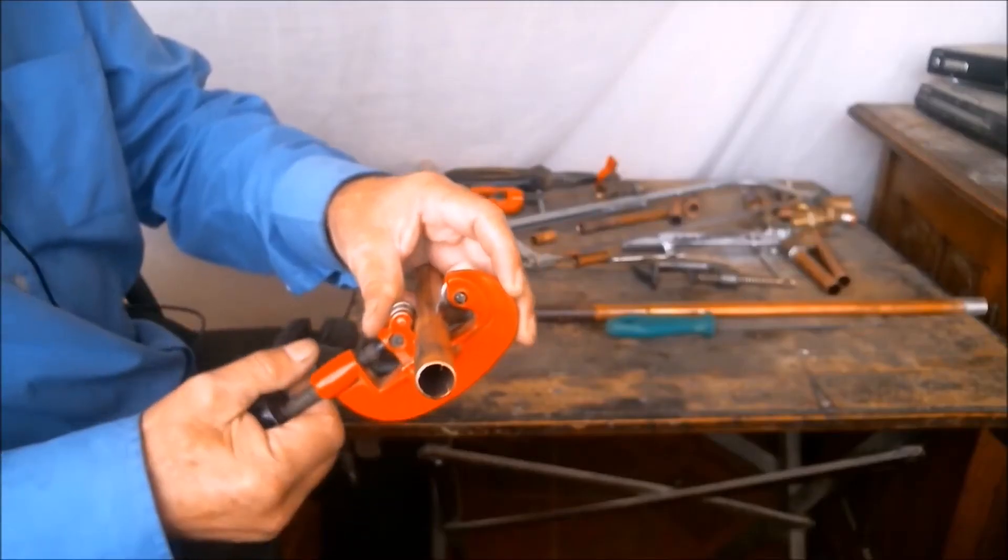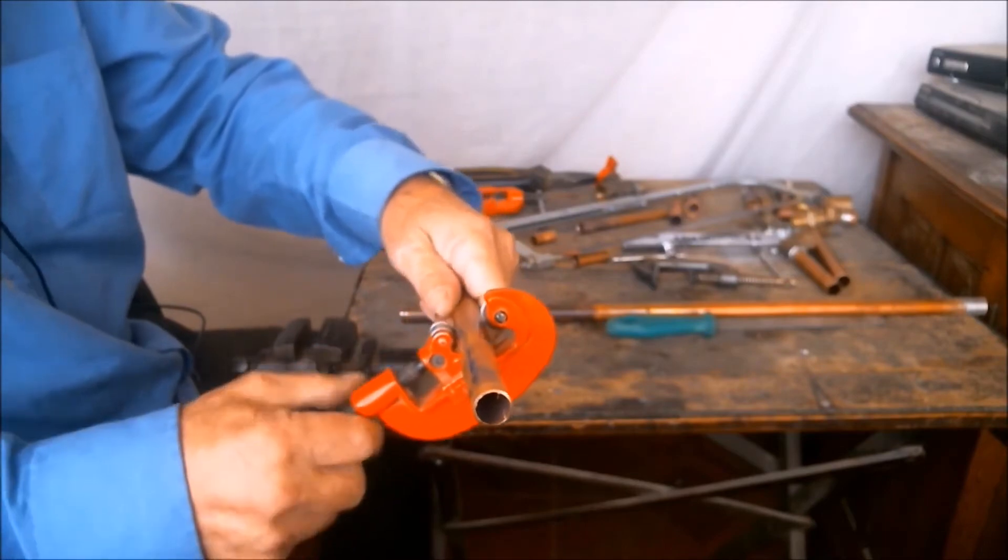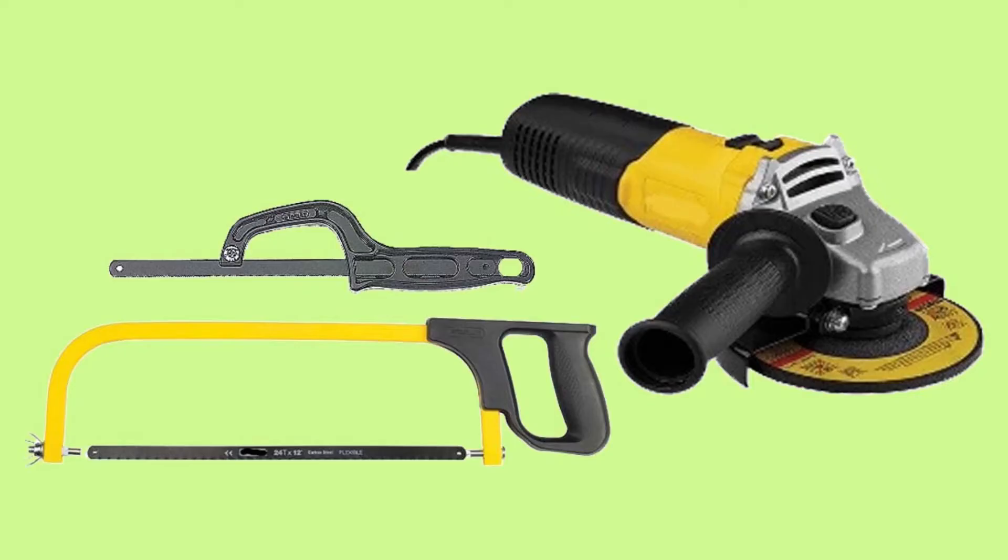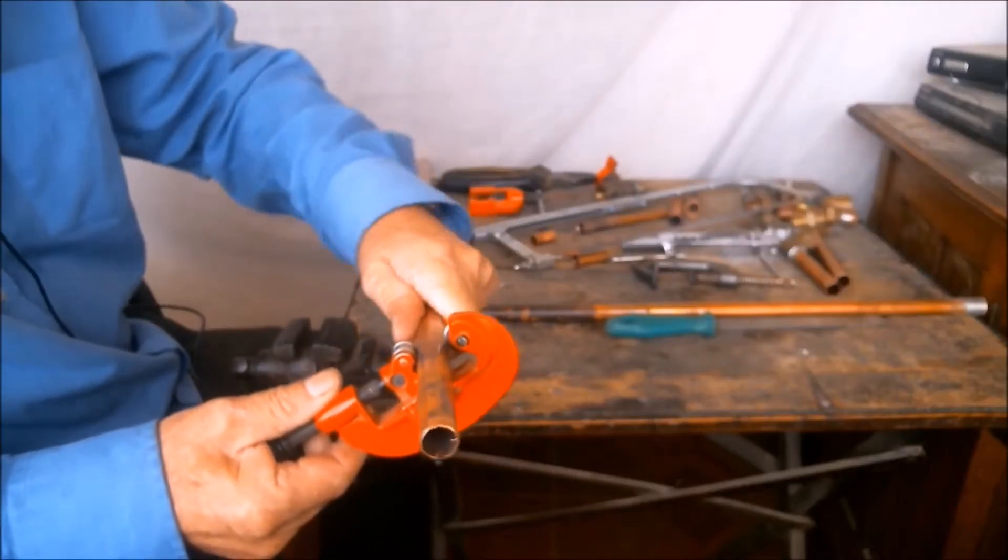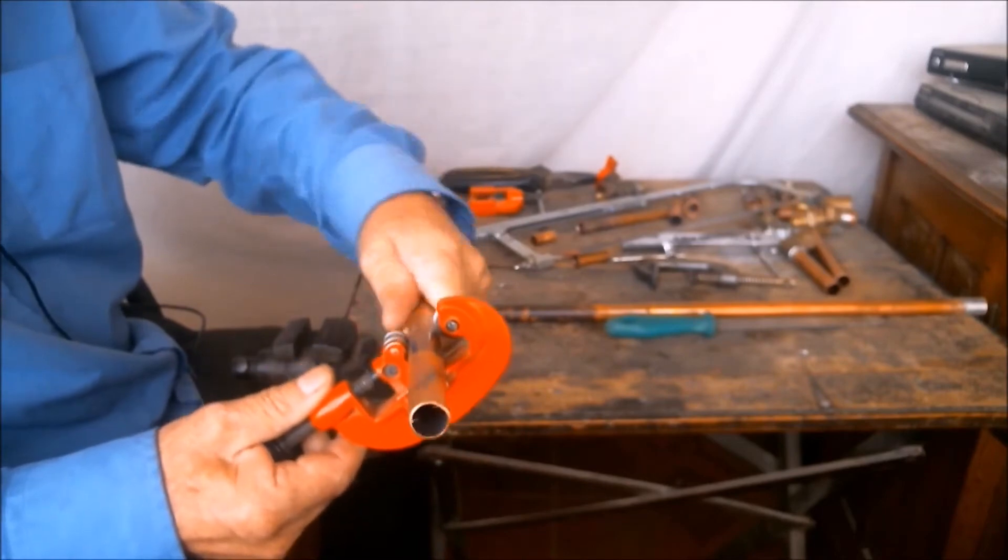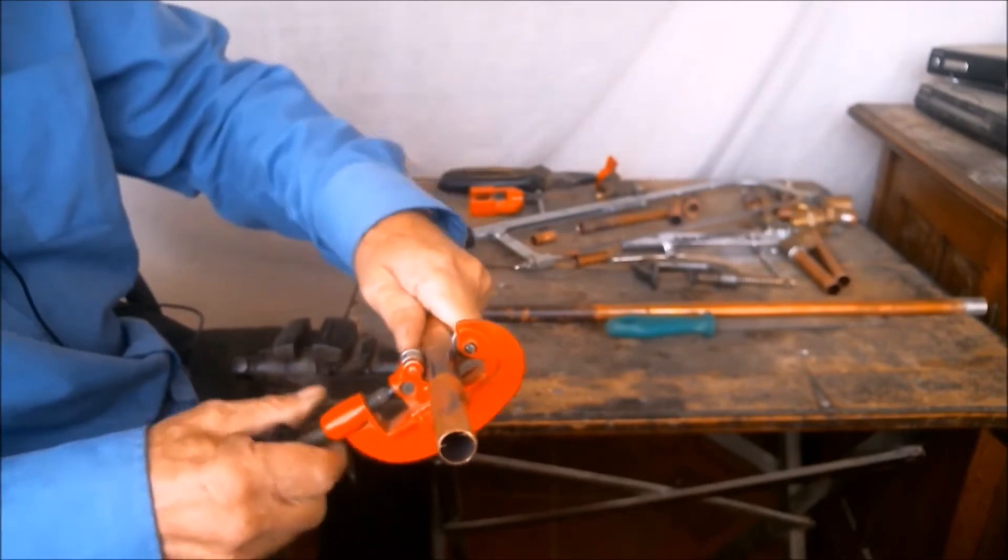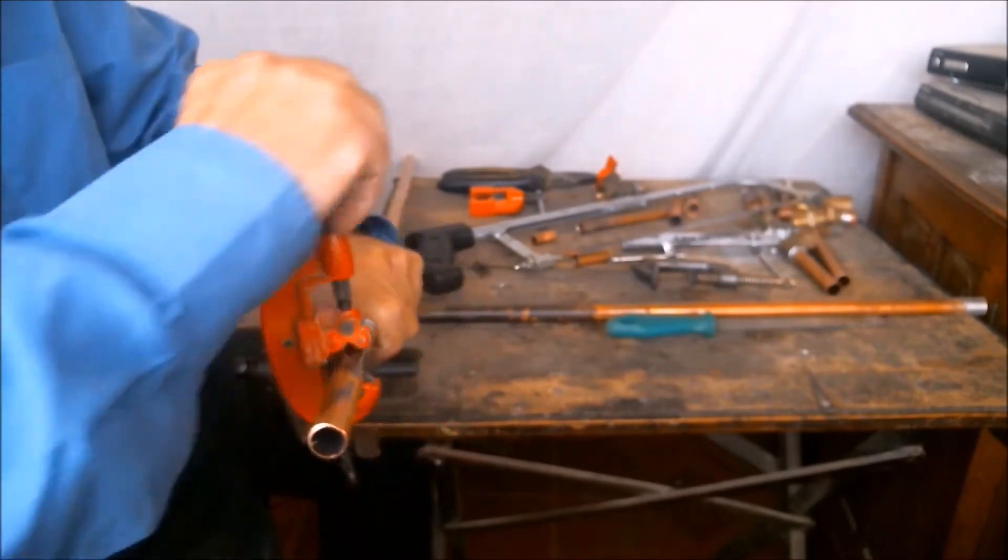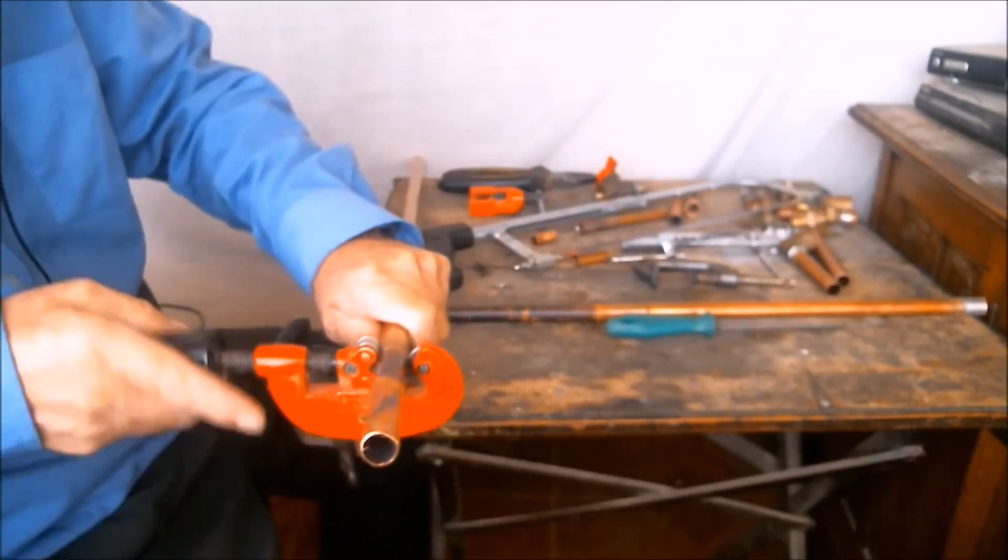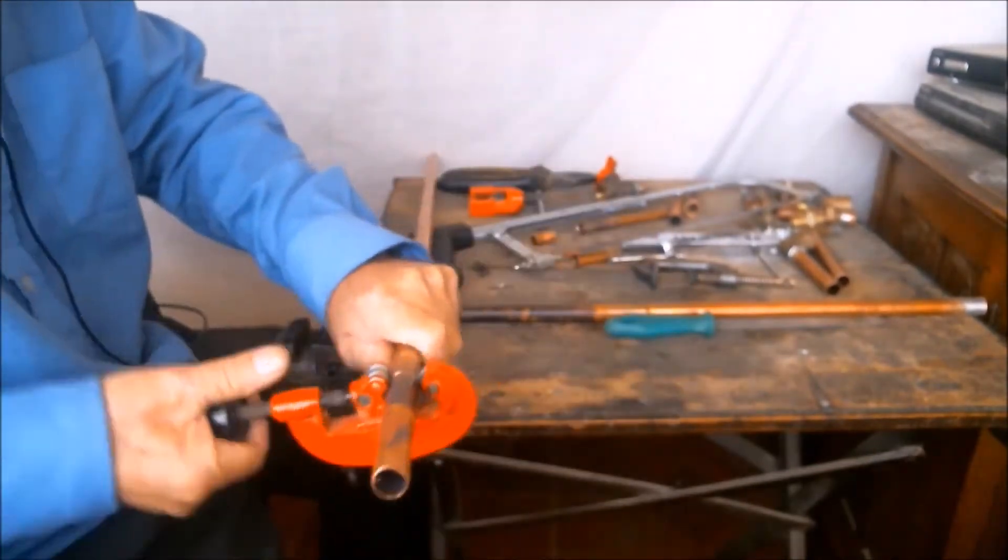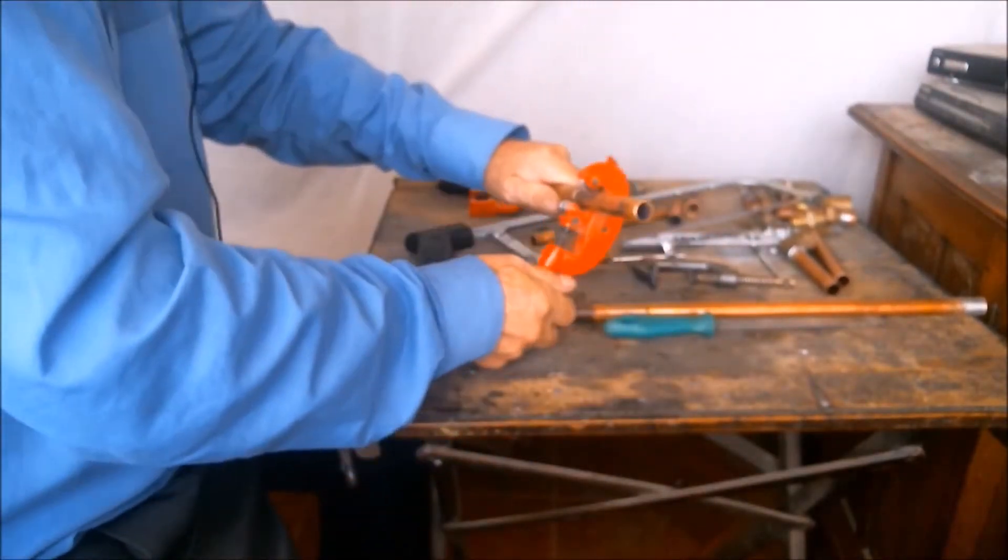To cut the pipe for flaring we must use a pipe cutter. Any other tool can give us a crooked cut. To make sure we get a 90 degree cut we first carve a slit all the way around the pipe. And then we start tightening the cut till it cuts the pipe completely.